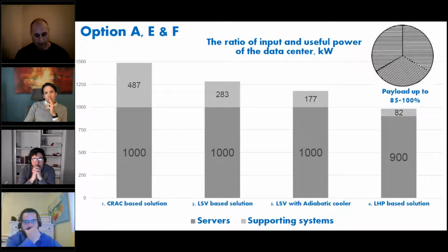And also the ratio of input power goes down, because the cooling system itself consumes much less, because we use higher temperatures for cooling the liquid, and in the third case we don't even need a chiller. This does not work with a conventional solution because there is a risk of overheating. For that reason we always need low temperature. But in the next example, I will show that we can work with the same servers with 30 degrees air in the cold aisle and no problem at all.